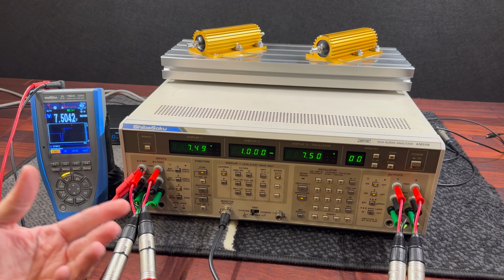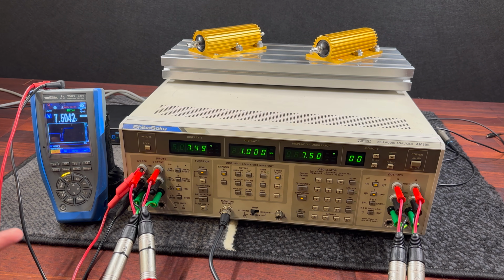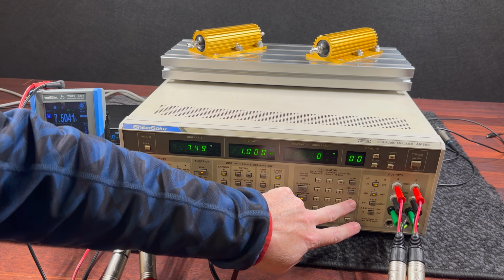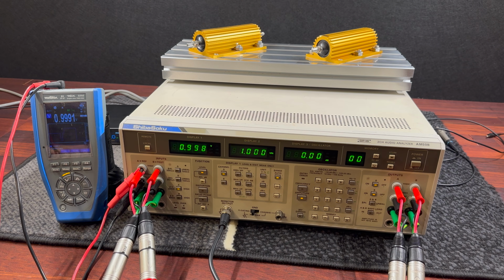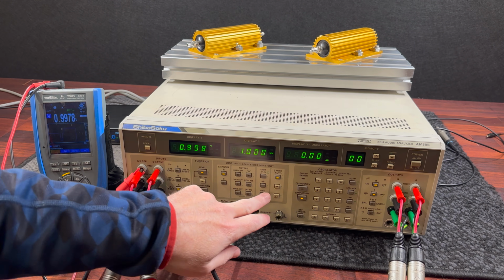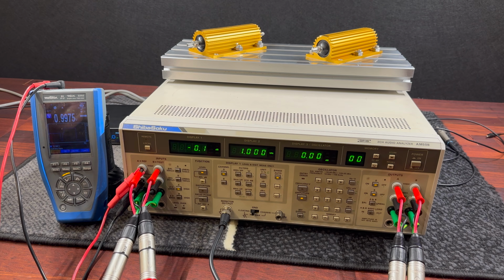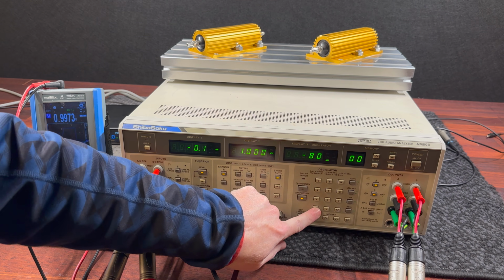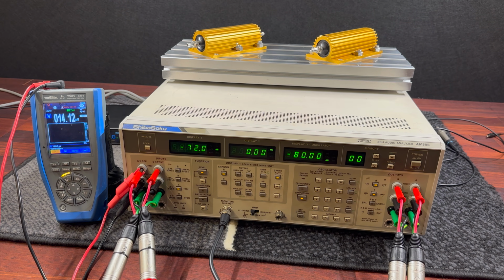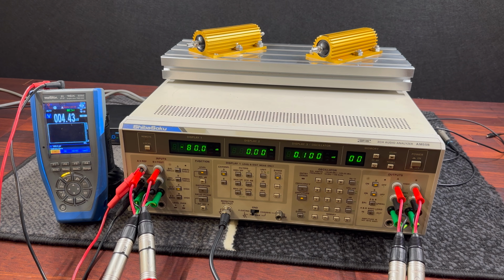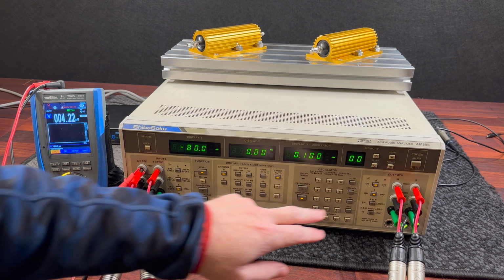So on the dB side of things, we have a 0 dB adjustment and a minus 80 dB adjustment. If I have it on 0 dB, which happens to be 1 volt, and then I switch to dB reading, we can see we're pretty much bang on there. The other adjustment is minus 80 dB, which I have done also, and there you go, bang on. Considering we are talking about 100 microvolts for this one, I'm quite surprised that this is within range.